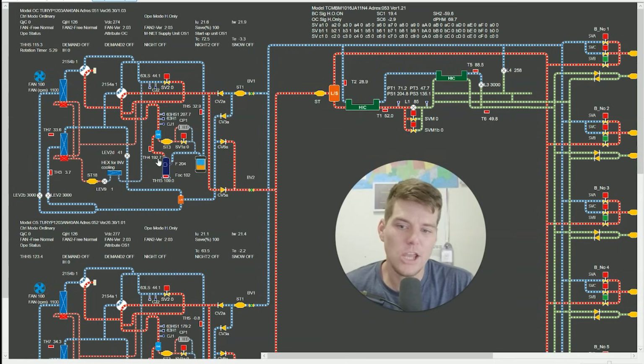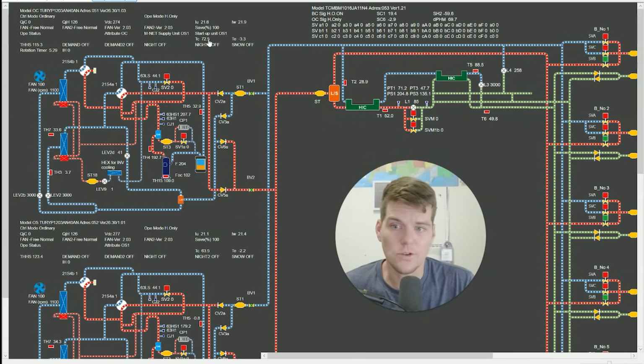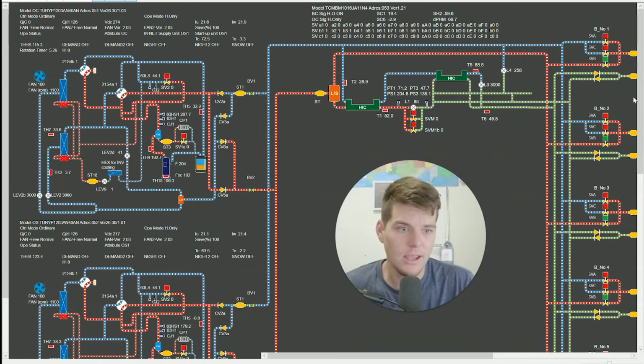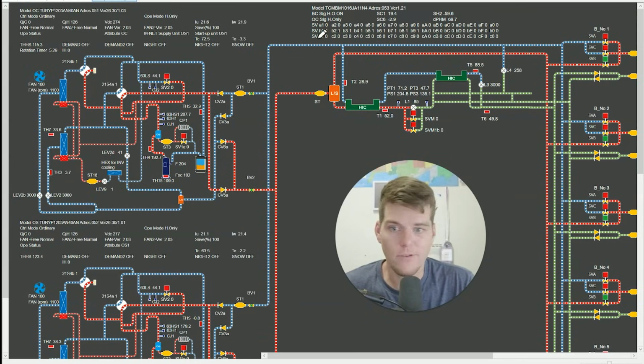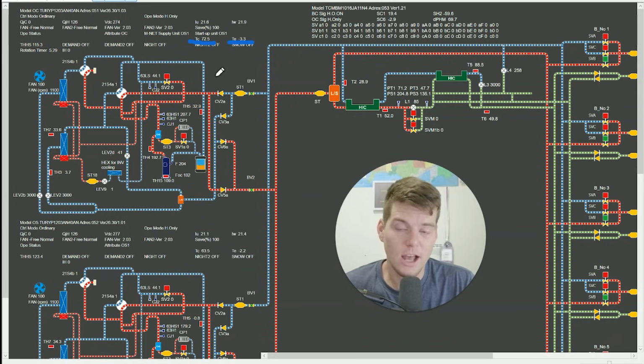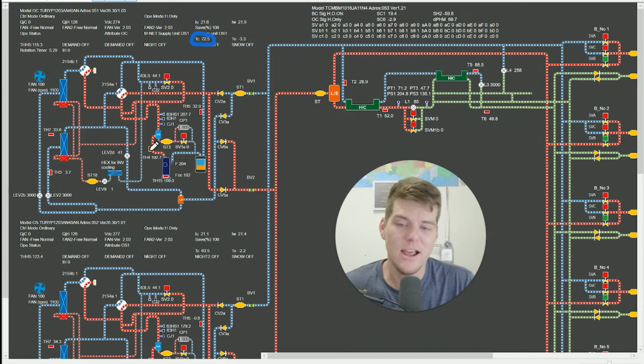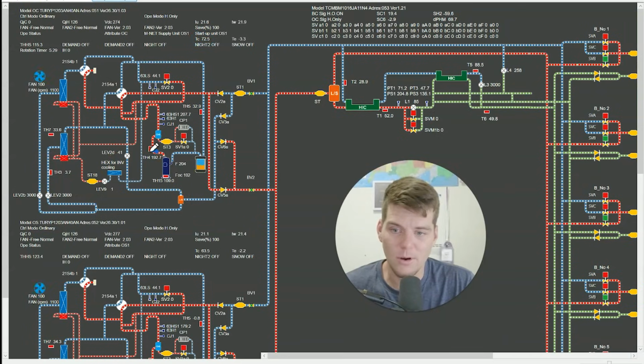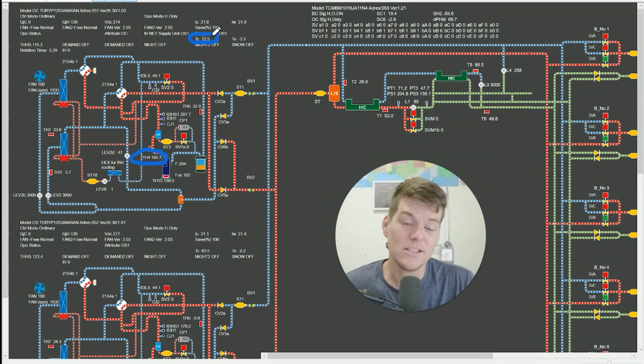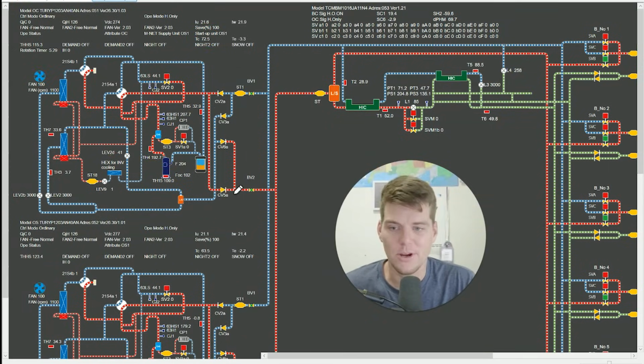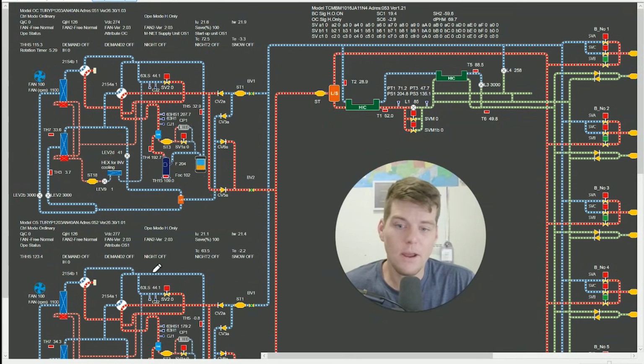So here we have TH4, which is our discharge temp off our compressor. So that's 192. So then I'd come up here and I'd look at, okay, what's my TC? And now I get to break out my fun pen, right? Your TC and your TE are up here at the top left-hand side. So my TC is 72. That's actually really low for heat. That's really poor heating output. And so if I'm 192 over 72, well, that's clearly over 100 discharge superheat. That's not good. What about my other module?